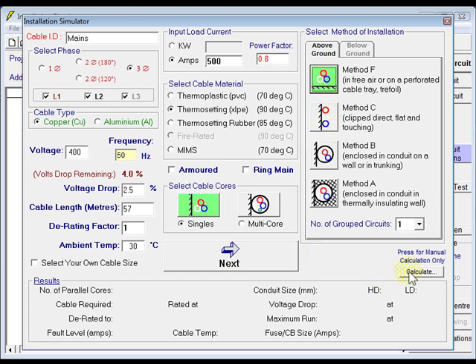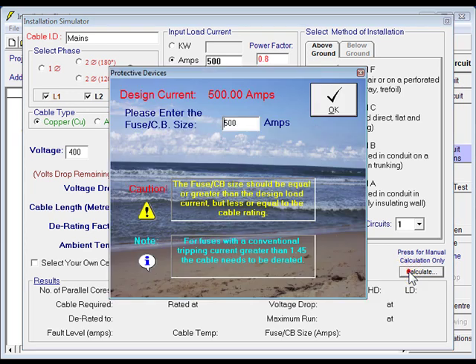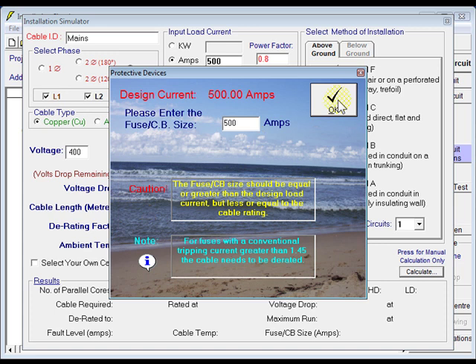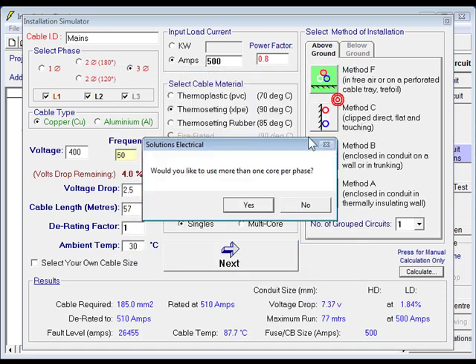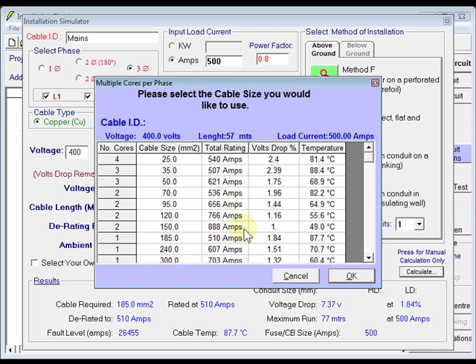We come down here now and click calculate. We've got a 500 amp circuit and a 500 amp CB, so we click OK. Would we like to use more than one core per phase, we can select yes here. There's many options to choose from. All our details are up there, we've got a 500 amp circuit, the length of the run is 57 meters, so we want something.